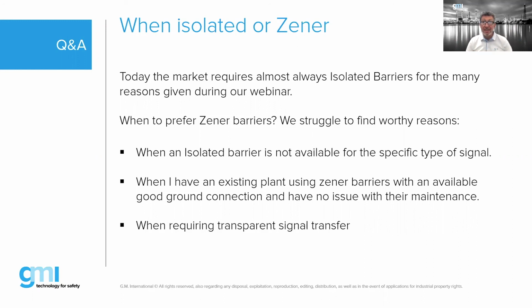And when there is an existing plant using Zener barriers, there's a lot of replacement. You already have a safety ground in the field. You might want to continue to use it. The space may be constrained or physically not allow room for an isolated barrier. And there is one required transparency in that. So basically, with a Zener barrier, they do not interfere with the signal. So if you get millivolt, you will get millivolt. With an isolated barrier, typically you get millivolt in, milliamp out. You can also have isolated barriers today that have millivolt to millivolt or ohm to ohm.